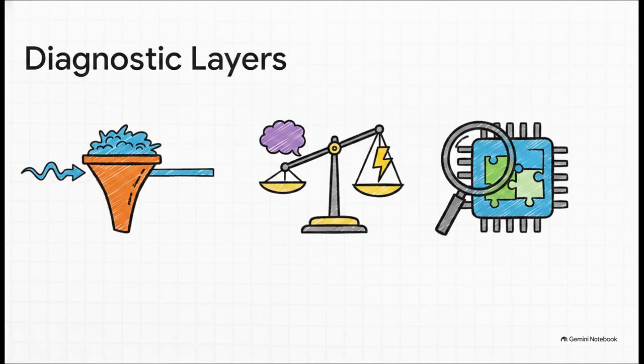To catch this, the system runs continuous layers of defense. We have highly isolated ESD ADC sampling chains running at a blazing 10 MHz just to filter out common mode interference. Then there's the PWM plausibility check, constantly calculating the math between predicted and actual phase voltages. If it sees a 10% mismatch lasting over 2 milliseconds, it flags a fault.